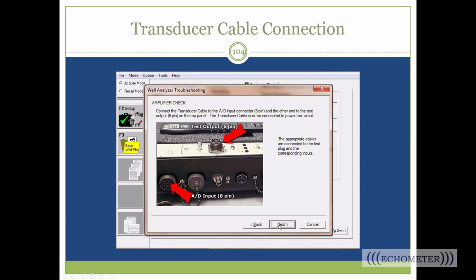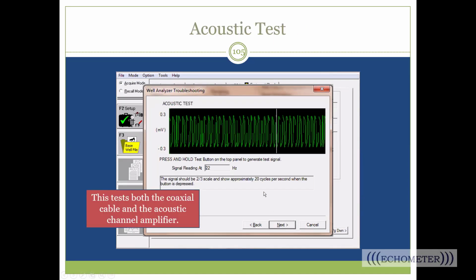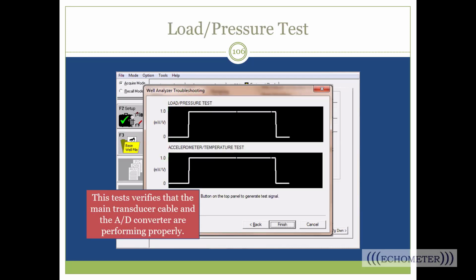Now when we click next, it's going to first do a check of your microphone cable. You'll see this thin green line going across the center of the screen. You want to press that little test button and hold it, and you should see that signal pop up. This is what you want it to look like. If you press that button and there's no signal response, then you've likely got a bad microphone cable. Then you click next.